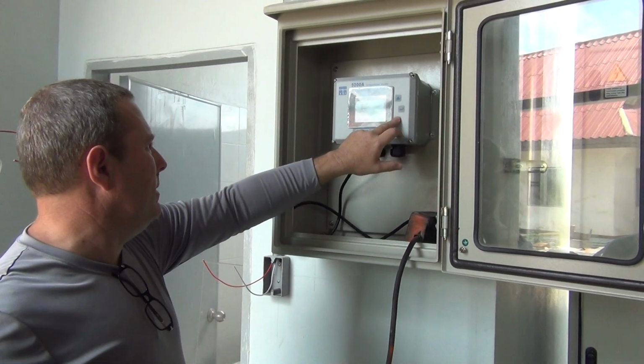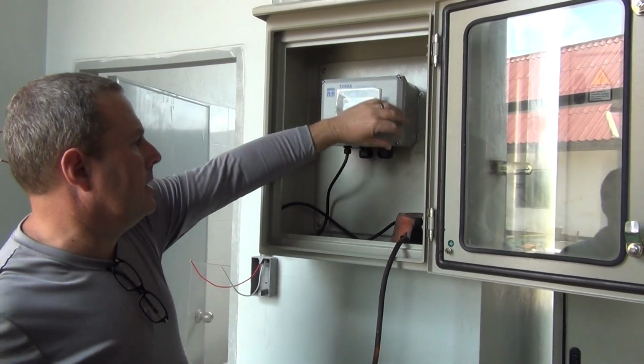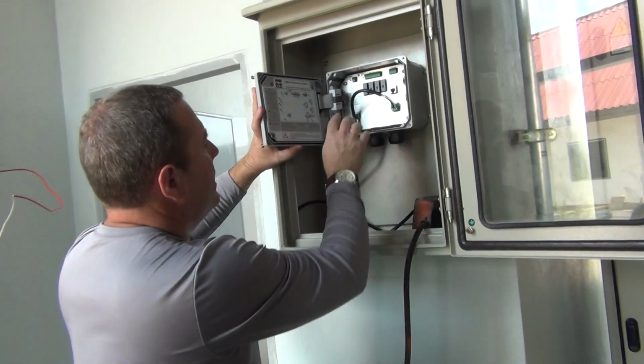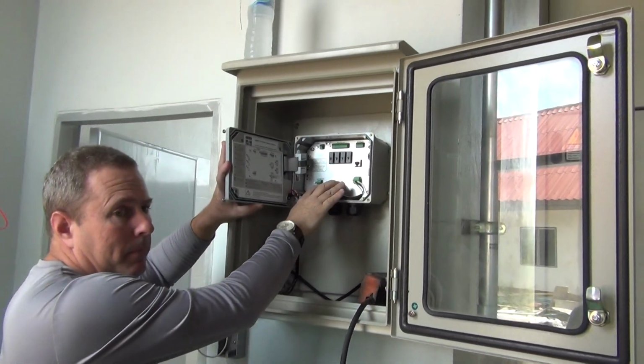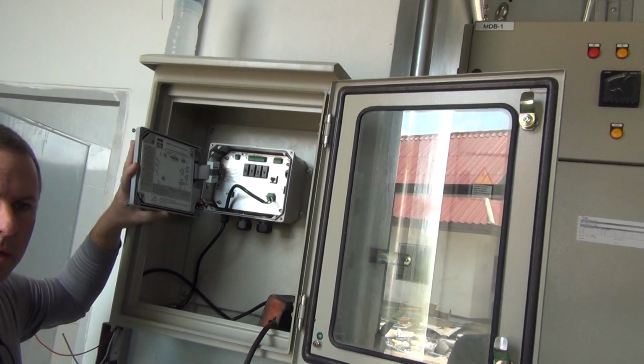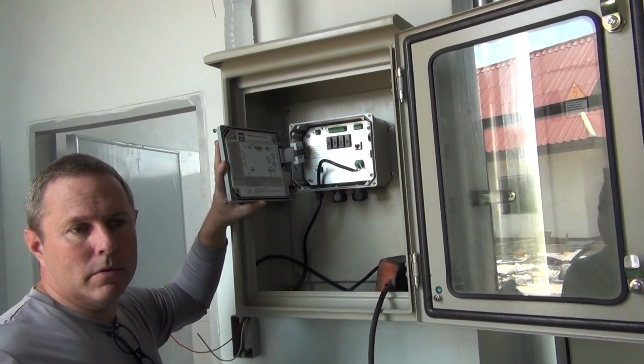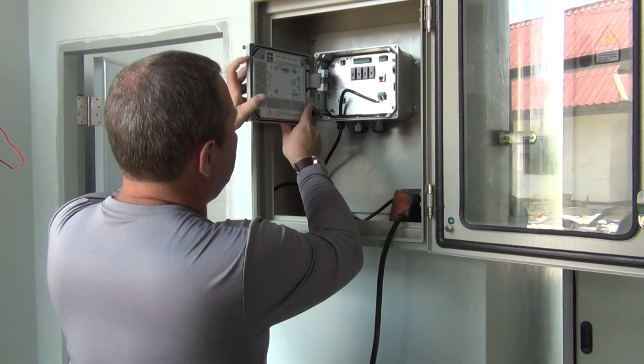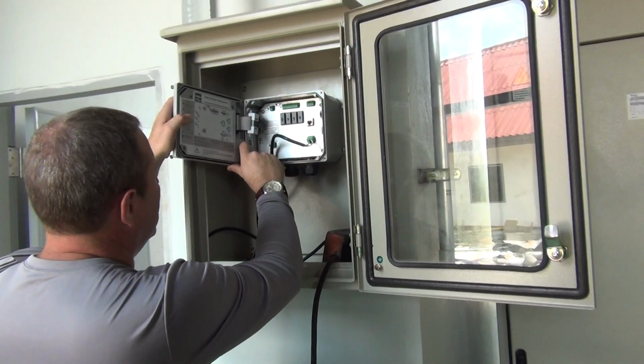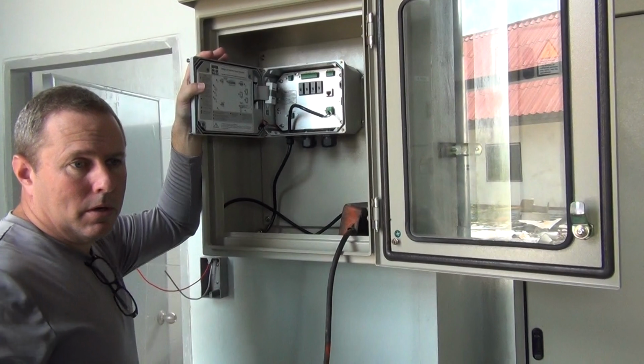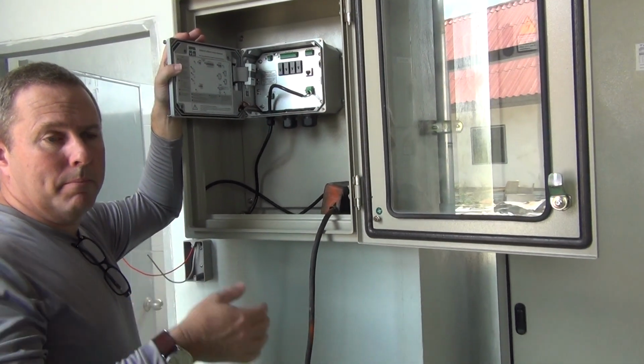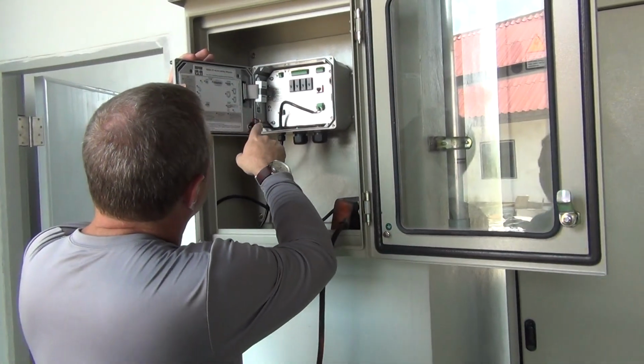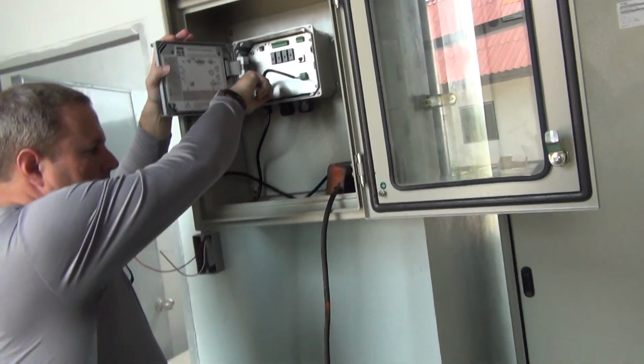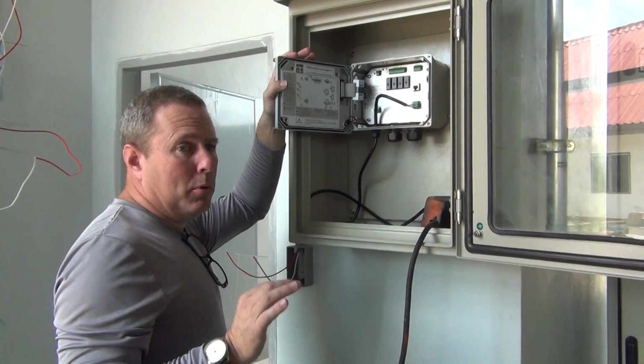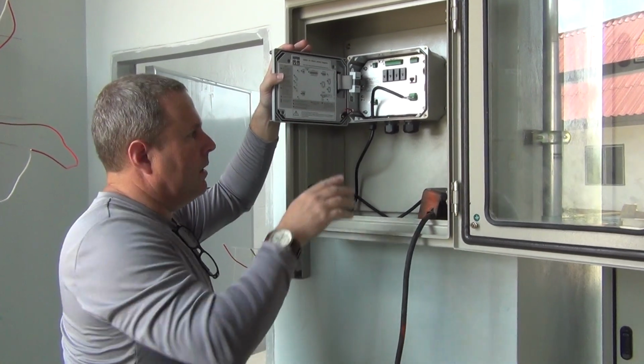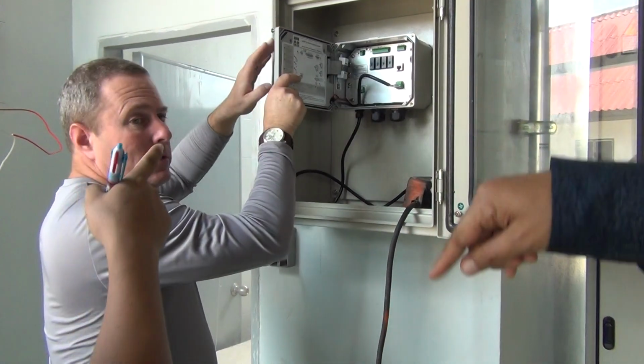So, the next items, it has auxiliary inputs right here. We have 2 inputs and a common. The inputs can be 4-20 milliamp loop. It can be 0 to 1 volt or 0 to 5 volt on/off. So, those are 2 additional inputs. If you needed more additional inputs, there is another box that goes similar that can do up to 8 I/O inputs, input and output 4-20 milliamp. We need to put a ground from this into your grounding system. That is important. It won't work properly without a good ground. So we're going to need to take a ground here and feed it into your system.